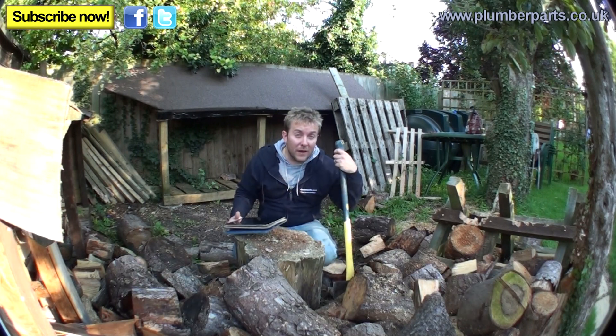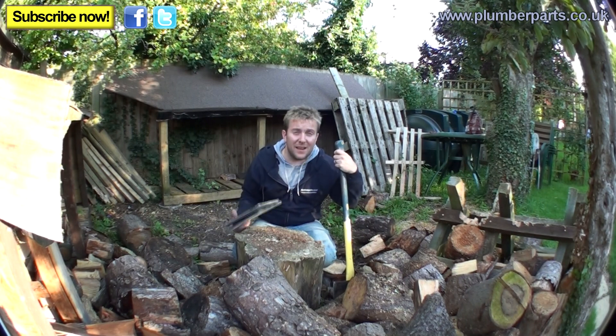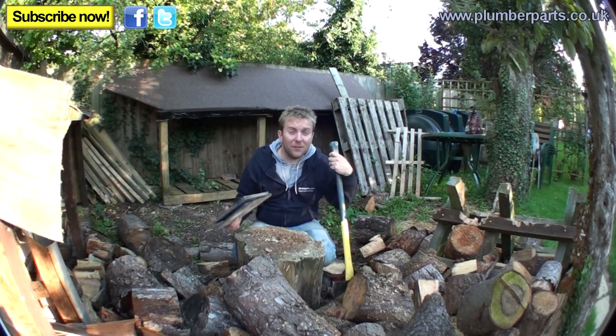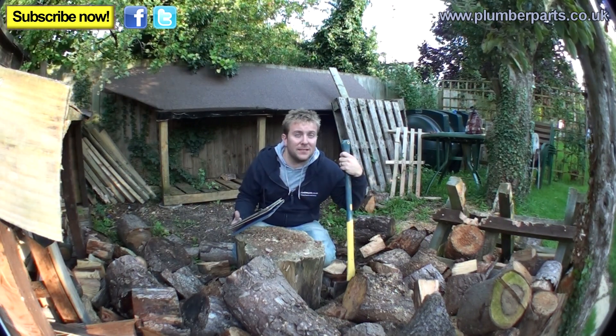If you've got a really, really small tank in your loft, he might well have to put a second tank in, because there's a risk you could drain the loft tank out. The shower pump would go dry, burn the impellers out, and ruin your shower pump. Also, depending on the complexity of the job, it could well take a day to fit. So it sounds like it could well be correct.